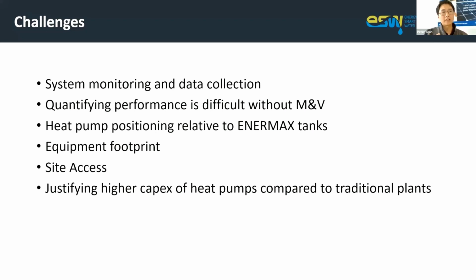Another major area we look at is equipment footprint and access. Heat pumps require a much bigger footprint compared to a gas storage or gas system, so we need to find a proper location with proper fresh air intake and cool air discharge, and chart a proper pathway to ensure the heat pump installation gets proper ventilation. Site access is also important, getting equipment from the ground floor all the way to the roof, since a lot of plumbing equipment is still placed on the roof. We need to keep in mind how to reduce installation cost while getting equipment up there.